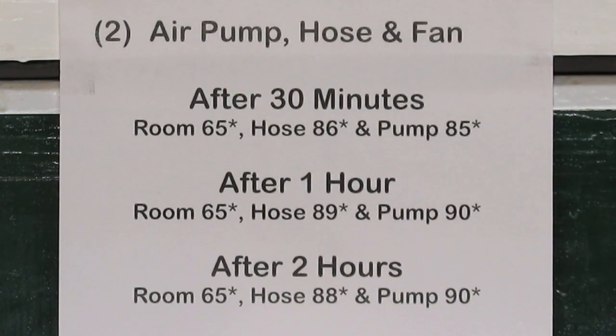In test number 2, the room temp stayed fairly constant at 65 degrees throughout the test. After 30 minutes, the hose temp was 86 degrees and the pump temp is 85. After 1 hour, the hose temp was 89 and the pump temp was 90. After 2 hours, the hose temp was 88 and the pump temp was 90. What can we learn from test number 2 as compared to test number 1? Both the pump temp and hose temp reduced by more than half over the room temperature. Also, a cooler pump might mean a longer pump life.